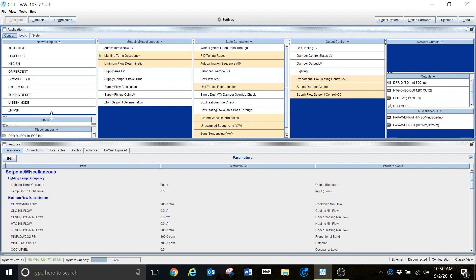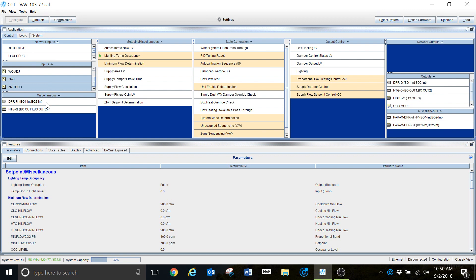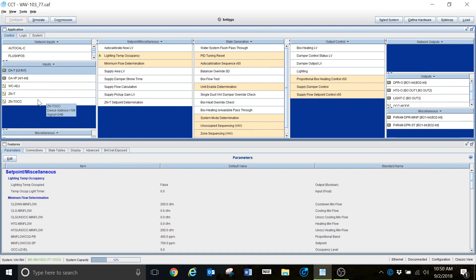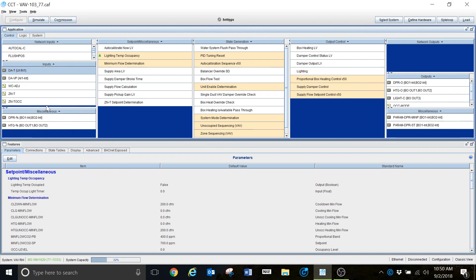The next block is going to be inputs. We have zone temp, temporary occupancy — that's what the TOCC is — warmer, cooler, adjust, and all of those. These are direct hardware inputs to that particular device. This is an actual sensor. This is the warmer/cooler adjust off of that sensor. You're reading velocity pressure, your discharge air temp — those are all inputs directly to that controller. That's something you're going to get very familiar with when working with any kind of PLC or controller like this.